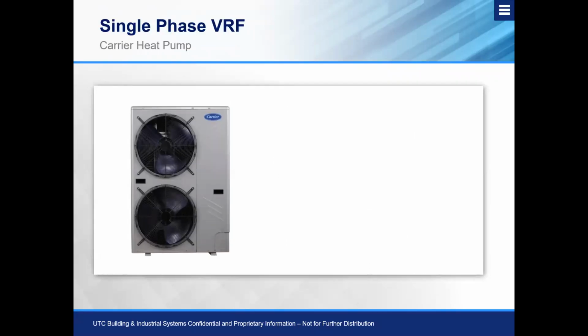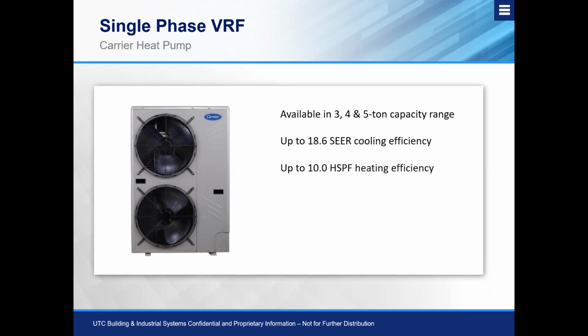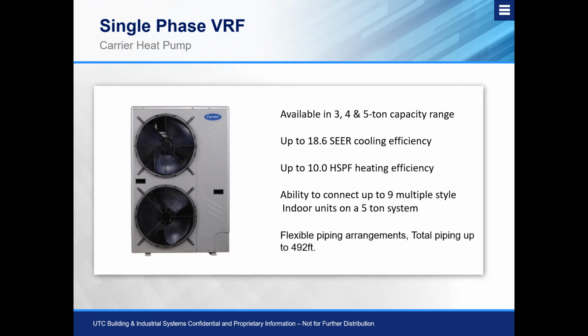Now, on the opposite side of things, when we look at the Carrier single phase heat pump, these are also available in a 3, 4, and 5-ton capacity range. We'll offer up to 18.6 SEER cooling efficiency, up to a 10 HSPF heating efficiency, and the ability to connect up to 9 multiple style indoor units on a 5-ton system. And again, just like on the Toshiba product line, these will depend on the tonnage of outdoor units. So the 3, 4, and 5-ton have a different number of total maximum connectable indoor units on that one outdoor unit. And we have a total piping length of up to 492 feet total.